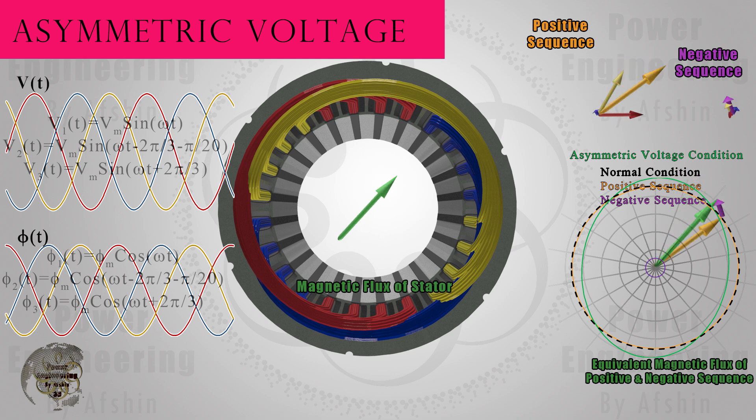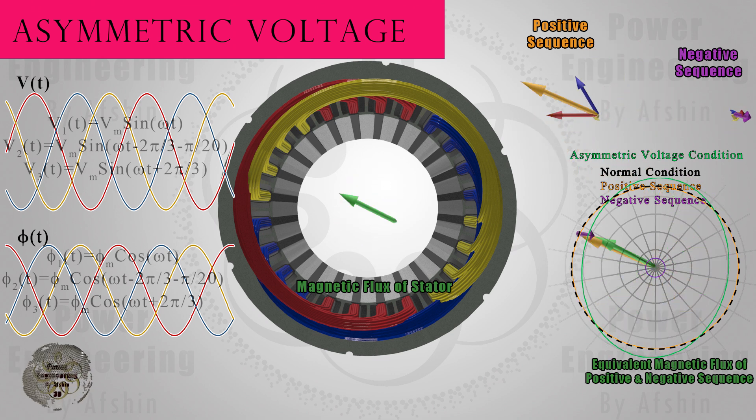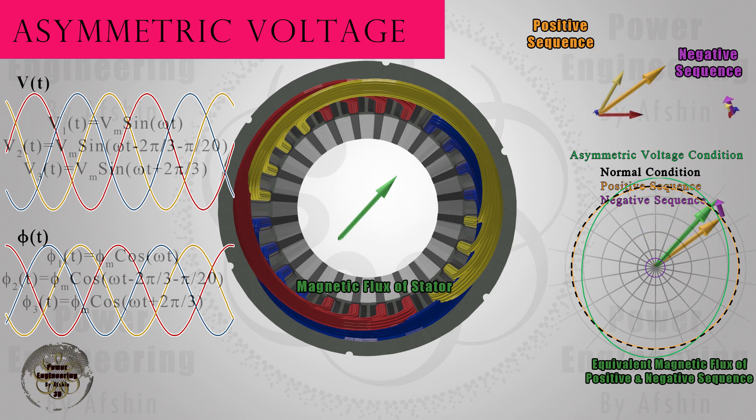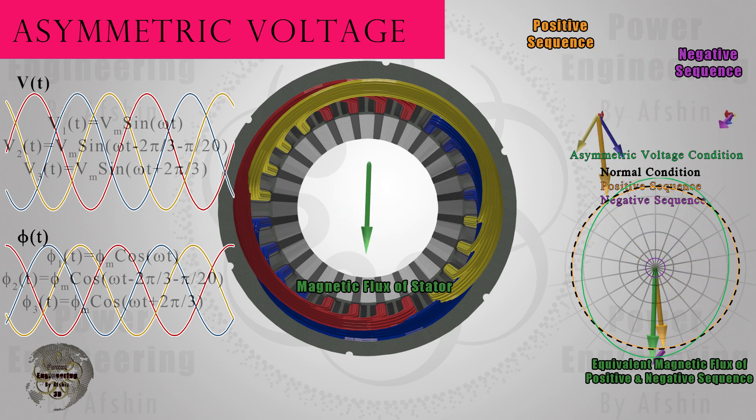It is clear that the negative sequence causes the rotating field to be non-uniform. It affects both its magnitude and phase. You can observe that for moments, the magnetic flux vector falls behind the positive component vector and then compensates for the lag. It is at this moment that braking torque is generated, leading to a decrease in motor efficiency and an increase in heat and losses.